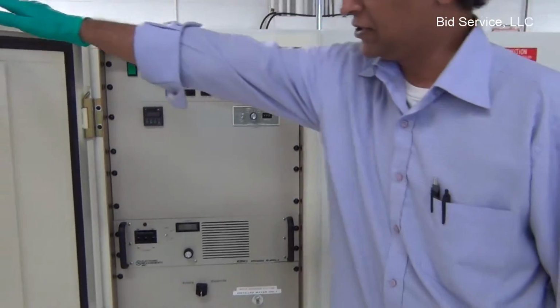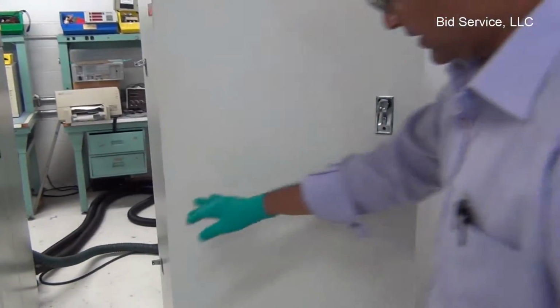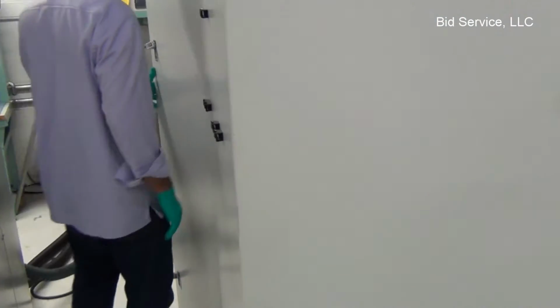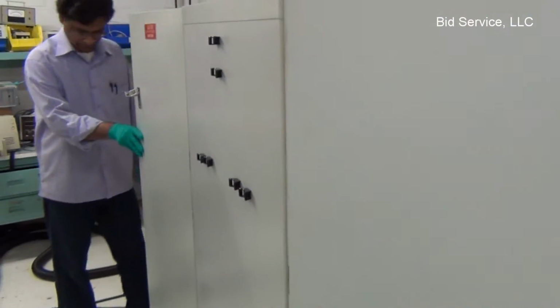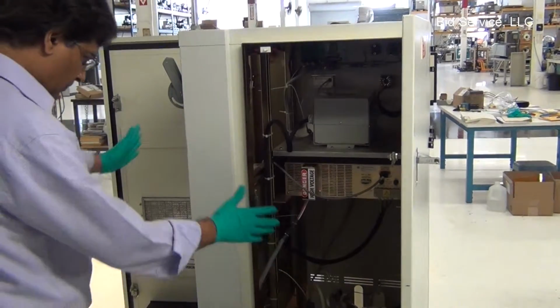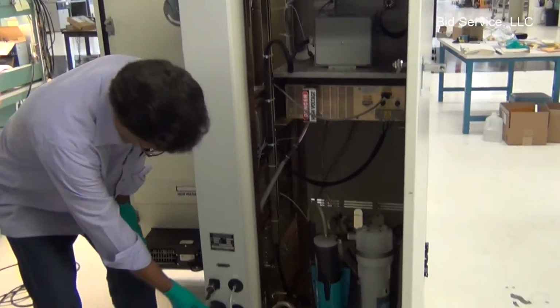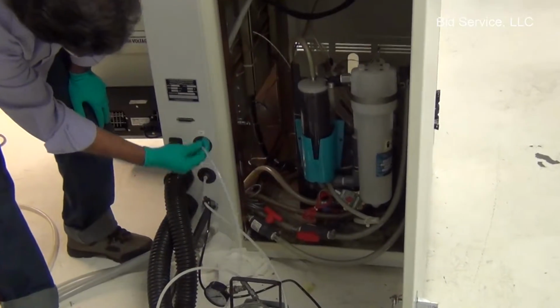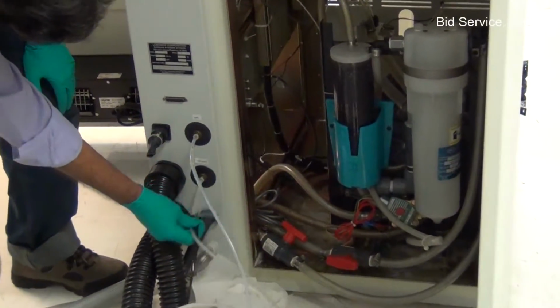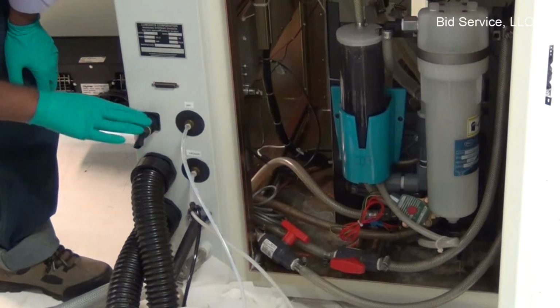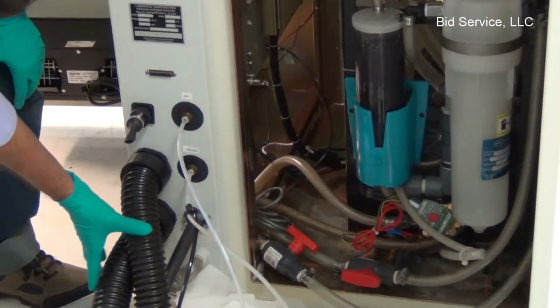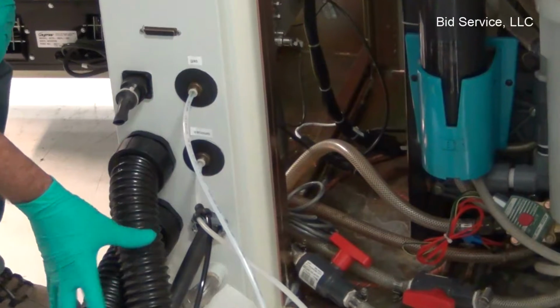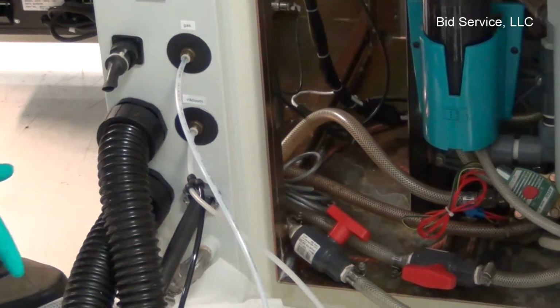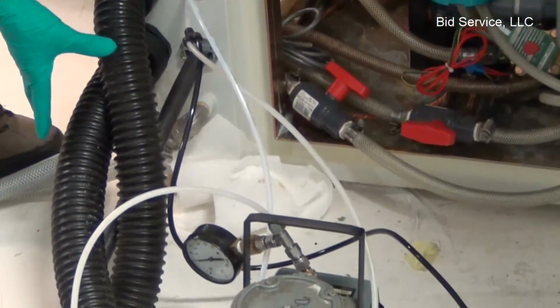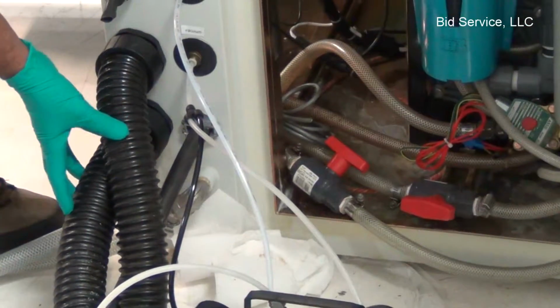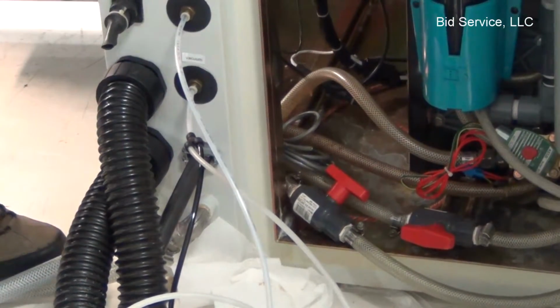Coming to the rear side of this system, this control panel is connected to the main machine. On the rear side, there's a gas connection line here, and there's a vacuum pump connection. This is just a jumper plug. And these two umbilical cords are to be connected to the main connector, main system, and these are hardwired. These cannot be disconnected on either end.